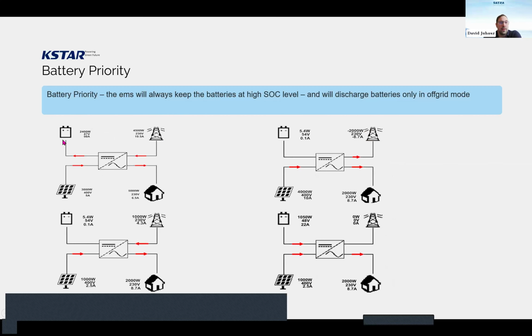Regarding the battery priority, the PV and the grid are together charging the battery. It depends on our consumption, because if we have this much, like 5,000 watts, and we have this 3,000 watt PV, and we are also pulling from the grid 4,500, the PV and the grid together are charging the batteries. And if there is an AC output on the system, the battery starts to discharge itself to feed the loads.